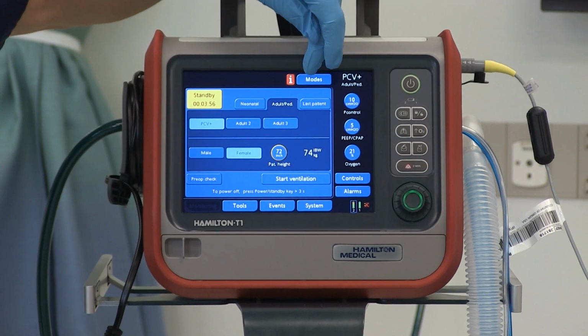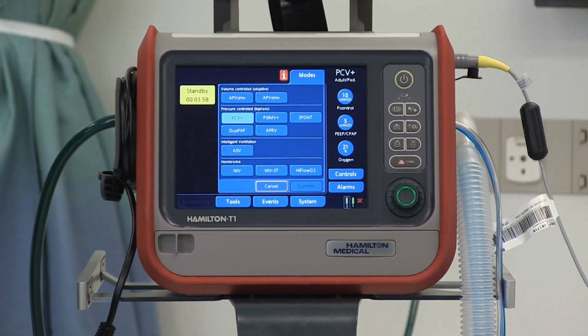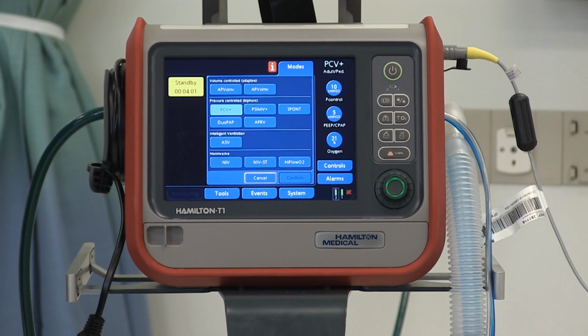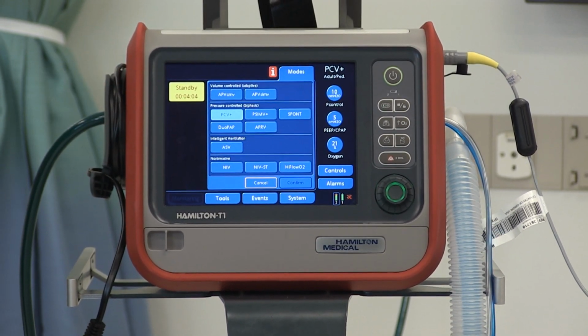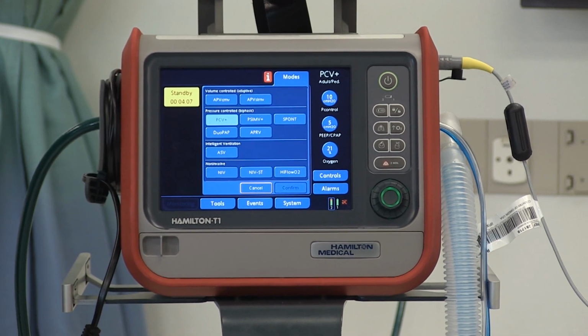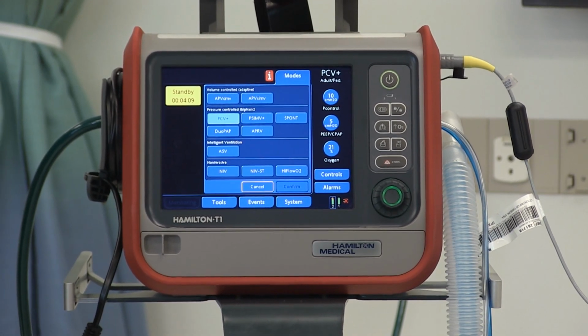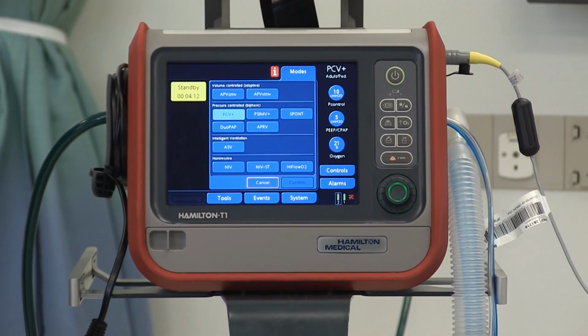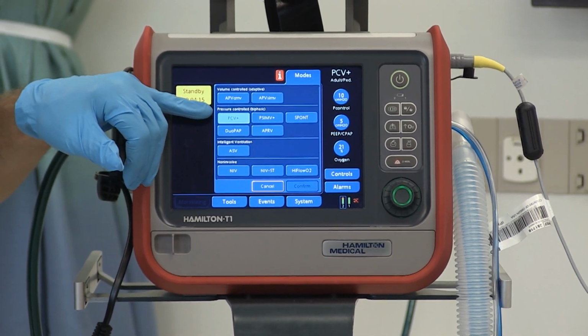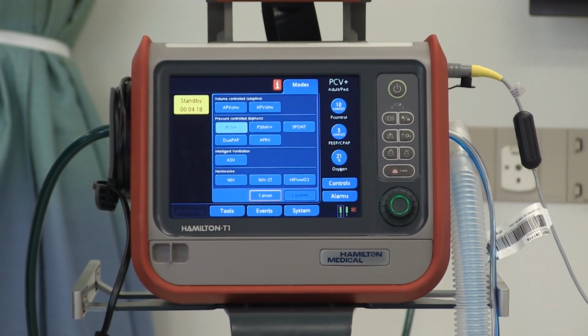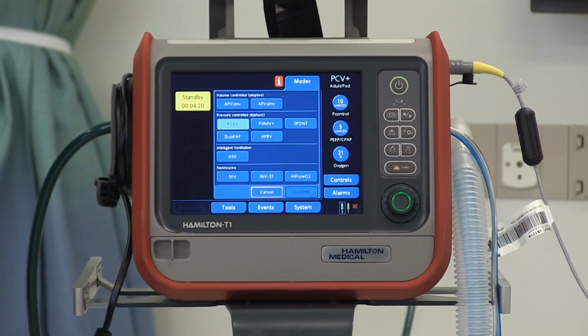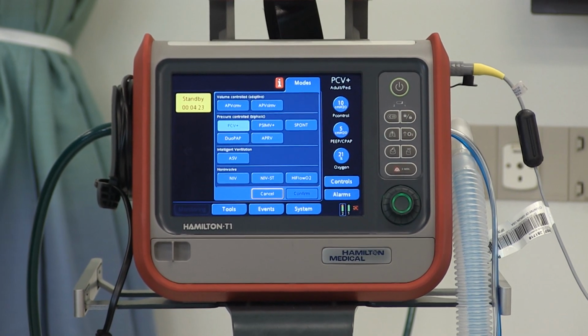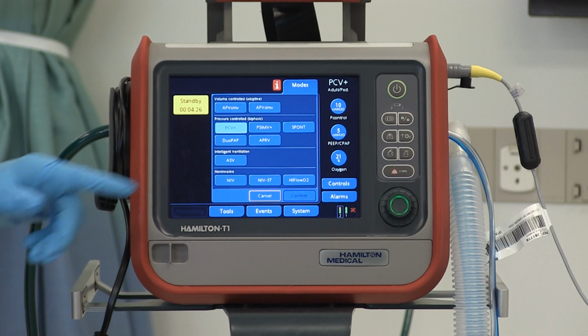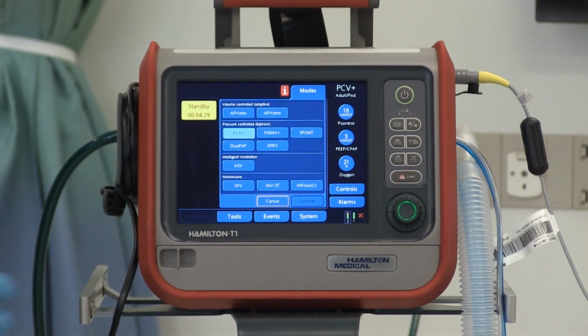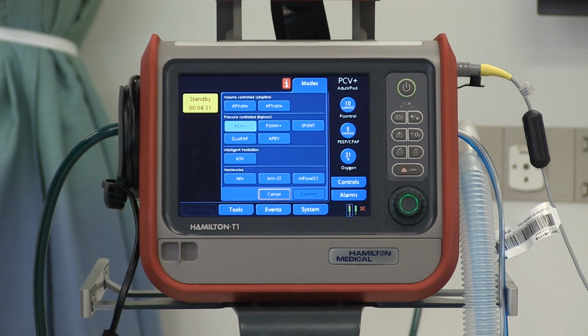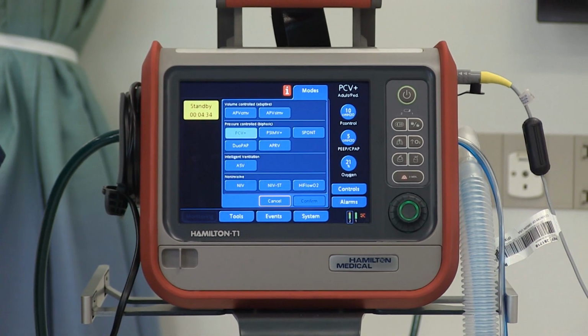If you would like to change modes before you start the ventilator, just select the Modes tab. Here's all the modes available on the Hamilton-T1. At the top, we have Adaptive Pressure Ventilation CMV and Adaptive Pressure Ventilation SIMV. Those are your volume modes. The next section down are your pressure modes. We have Pressure Control Ventilation Plus, Pressure SIMV, Spontaneous, and two forms of bilevel called DuoPAP and APRV. Below that is a mode called ASV, which is Adaptive Support Ventilation. That's a mode that's unique to Hamilton Medical ventilators. It's a closed loop mode of ventilation.